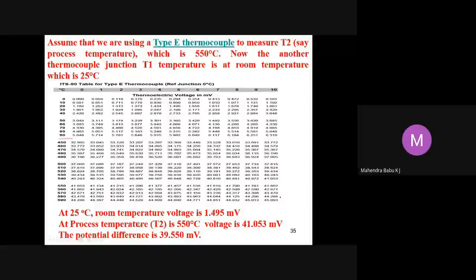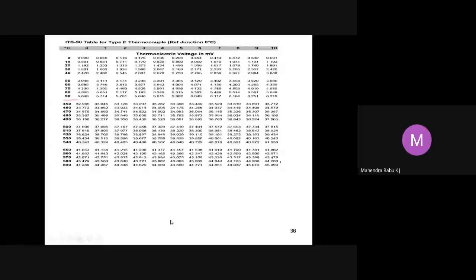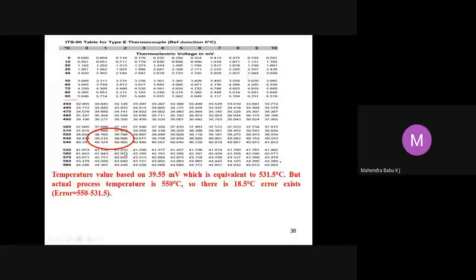Now the potential difference, that means the voltage difference between these two, one at room temperature and the other at process temperature. If you take the difference in voltage between these two, the potential difference is 39.55 millivolts. Now, what is the temperature corresponding to 39.55 millivolts? You can see that 39.55 comes in between these two readings, 530 plus 1 and 530 plus 2, that is 531 and 532. So you have to interpolate between these two, and you will get approximately 531.5 degrees Celsius. So the temperature value based on 39.55 millivolts is equivalent to 531.5 degrees Celsius.